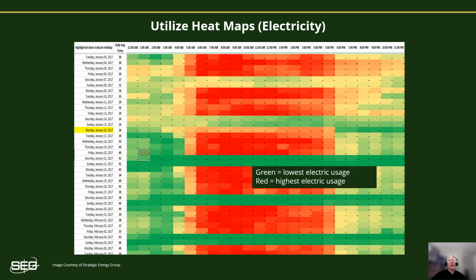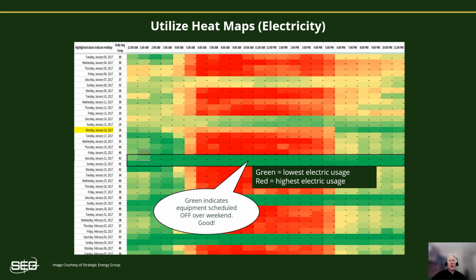Heat maps are another great tool for verifying building performance. In this graph, the vertical scale on the left is for each day of operation, while the horizontal scale across the top shows each hour of the day. The green represents low energy consumption and the red indicates higher consumption. Note how the operating patterns are quickly discernible. Evening and weekends show up as green versus bright red for the occupied time of the week.